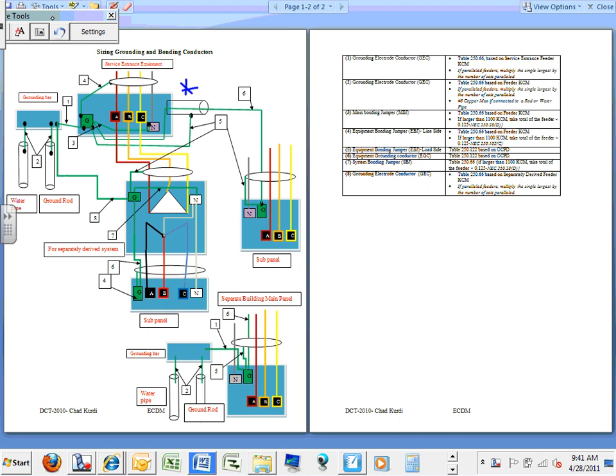Spencer, I went and fed a receptacle panel. You guys have done that with me. To a transformer, we feed the receptacle panel from the same service, which is this one. This is my receptacle panel to a transformer. This is my lighting panel or mechanical panel. And also from the same service, I fed a different building, a second building, with a feeder.